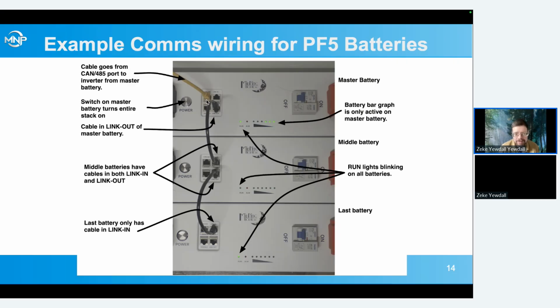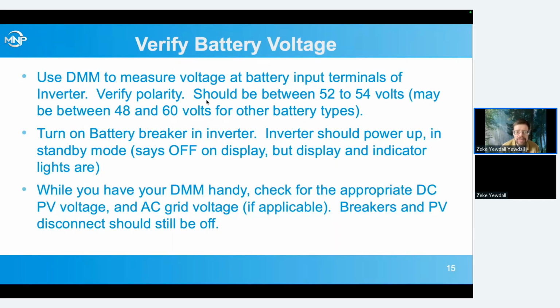Now we want to measure our battery voltage. Take our digital multimeter and measure the voltage at the battery input terminals on the inverter. Verify our polarity. Make sure we've got both the polarity and appropriate voltage there. And now we want to turn on the battery breaker in the inverter.